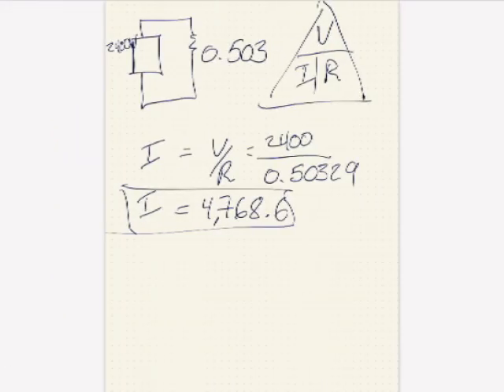So these faults result in incredibly high amounts of current flowing, far in excess of what the equipment is rated for. Remember, the equipment is rated for maybe 600 amps if it's a full-scale feeder. And so this sort of a current flow is going to be delivering a lot of excess heat. It's going to be delivering a ton of energy into that fault point. It's going to be causing some significant damage, not just at the fault, but it's going to be overheating all the assets all the way back to the station and putting additional stress on those as well. So we're going to pick up on that thought in the next set of videos.